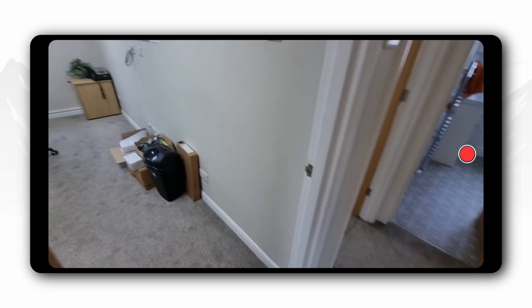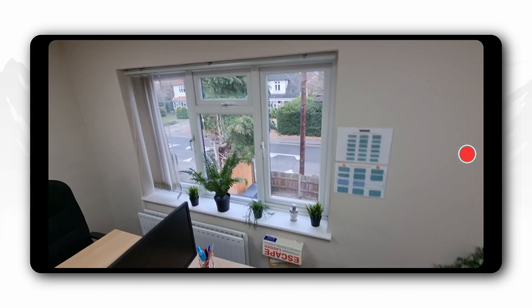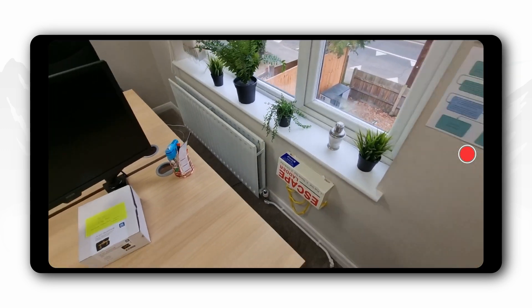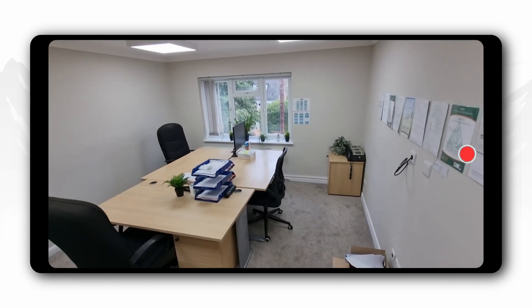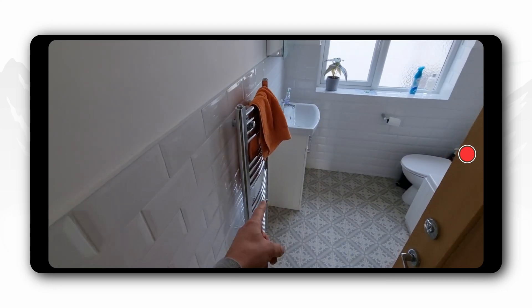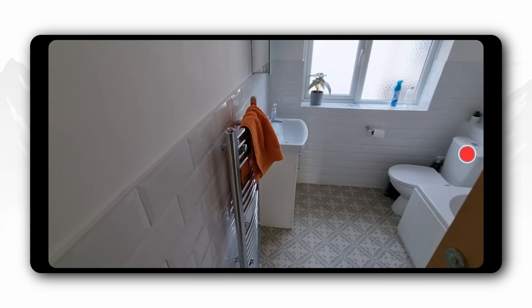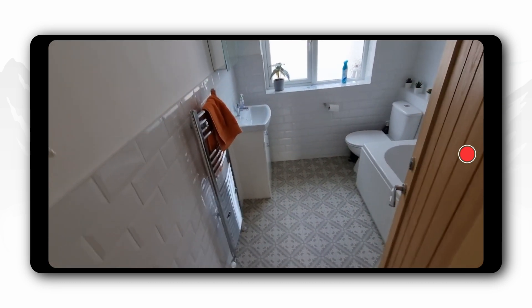In this room in here, we have a shortened radiator, not as wide as the window — so probably much smaller than in your typical house. Double panel, single convector, very small little radiator, smaller than most radiators, smaller than average I would say. In here, we haven't even got a standard radiator, we've got a tower radiator. As opposed to having like a kilowatt or two output, that's got about 300 watts. So it's tiny — very normal, but probably slightly small for this bathroom.